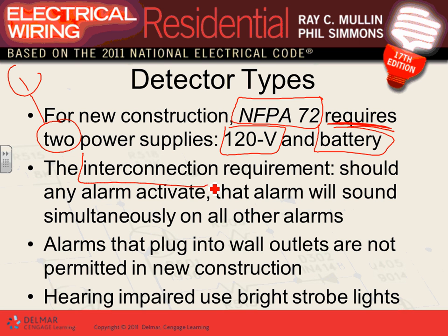Requirement number 2, interconnection requirement. They use 14-3 cable between the smoke detectors: the black, the hot, and a neutral to power them, and a third wire, typically red, comes with it. That third wire sends the signal. If one of them goes off, it will send the signal on the third wire to turn each and every one of them on. Can I have a thumbs up, Chad?